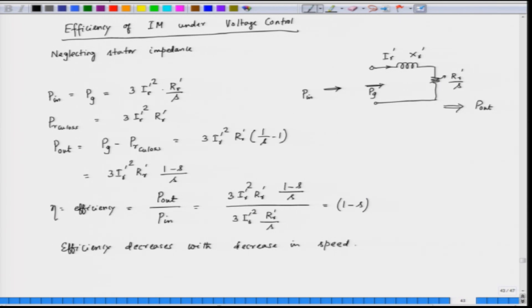This is the control of induction motor by voltage control, which is applied for low power applications — primarily fan applications where efficiency is not a very big issue. For high power, voltage control is not preferred because when we use voltage control and the speed is low, efficiency decreases. So for higher power we should have better ways of speed control. What we do at higher power is voltage and frequency control — we control both voltage and frequency.